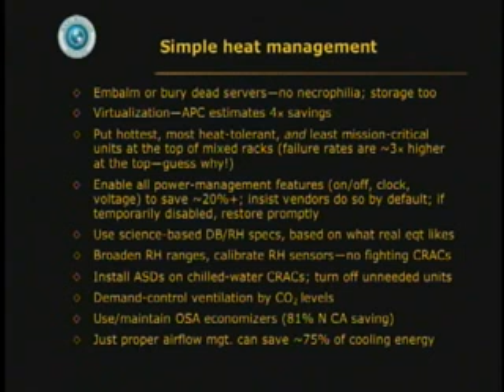DC power supplies. In Switzerland, they saved about half the energy. Lawrence Berkeley measured a little smaller savings. But the Japanese get big savings out of this with an order of magnitude better uptime. They do it in over 10,000 installations because their main installer happens to be a telco firm. In fact, you could use a distributed uninterruptible power supply, just like a lot of laptop batteries.